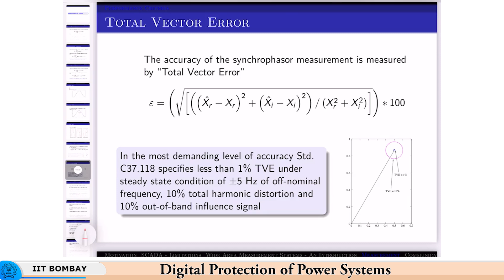If you see here in the small diagram, the small circle, this is the phasor, okay, the actual phasor, and if the TVE is 1%, then it can lie anywhere in the small circle that you can see, and if the TVE is 10%, then it can lie anywhere within the large circle that you see. Okay, so total vector error equal to 1% is the level of accuracy that is specified in the IEEE C37.118 or the synchrophasor standard. Again I repeat, if you have access to this standard in your colleges or institutions or wherever you are working, please go and have a look. It will clarify a lot of concepts.